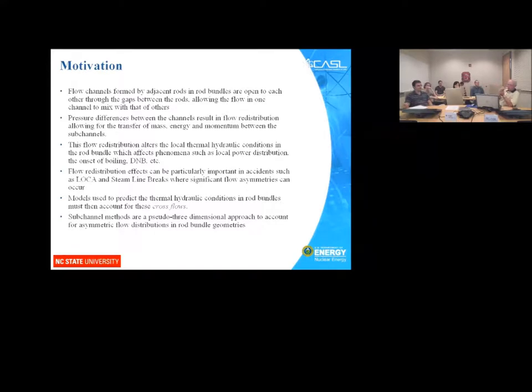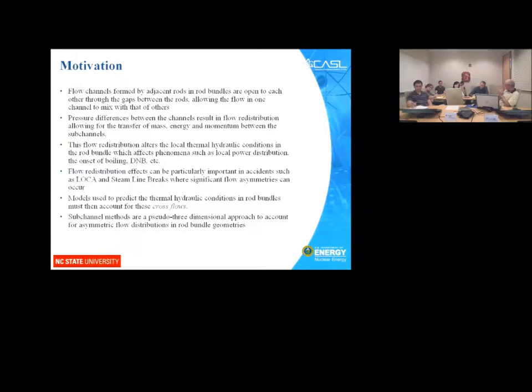To calculate these phenomena, we need to predict cross flows — flow transfer from one sub-channel to another through the spacing between the rods. Sub-channel methods are restricted to rod bundle geometries. They are a pseudo-three-dimensional approach and cannot be used to predict three-dimensional flows in an open volume. The models are derived particularly for rod bundle geometries, not general open spaces.